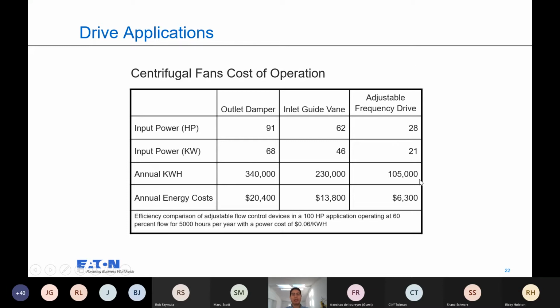This is a good example. So on a 100 horsepower application, operating at 60% flow with roughly 6 cents per kW hour, 5,000 hours per year. If you're just using a damper valve, this would be your consumption at a year, 20,000 versus using an adjustable frequency drive. There's instant energy savings here on just a simple 100 horsepower application as an example. Obviously, there are energy savings achieved through vanes and dampers, but not nearly as much as you could achieve with a VFD.